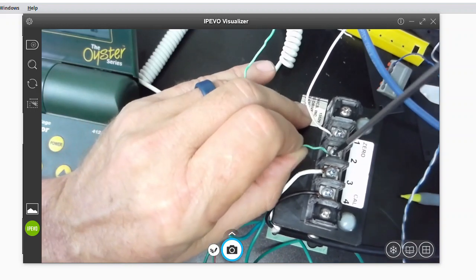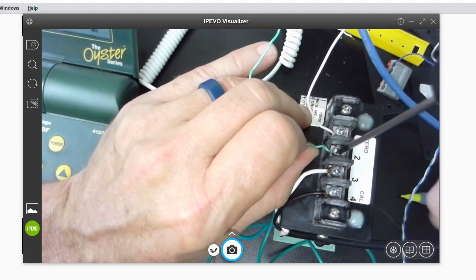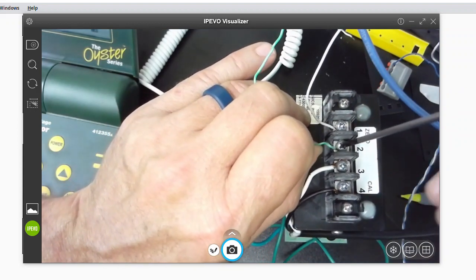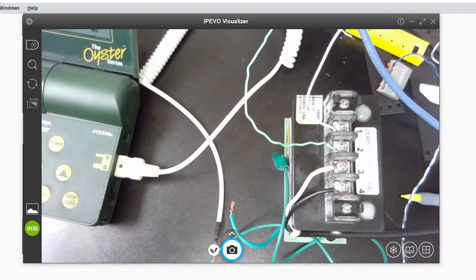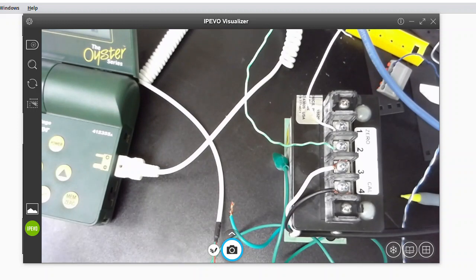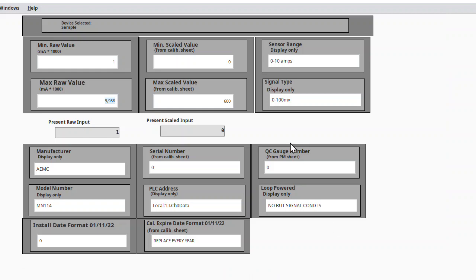And now I'll be honest with you, some of these Ohio sensors have quite a bit of millivolt bleed off. This one is powered, so if there's no power, there shouldn't be any bleed off, because the electronic circuitry is not powered up. So we're going to go see what our signal is. Right there. We'll see that, yep, we're still floating at 1, so our card is just a tiny bit out of whack. So our present raw input is 1. Everything looks good. It's floating just a tiny bit. That's fine. So it says 0.